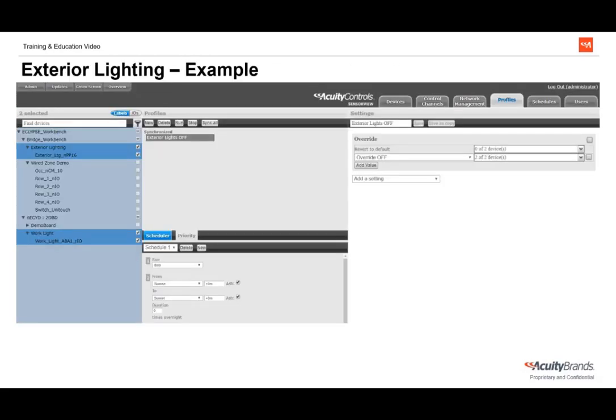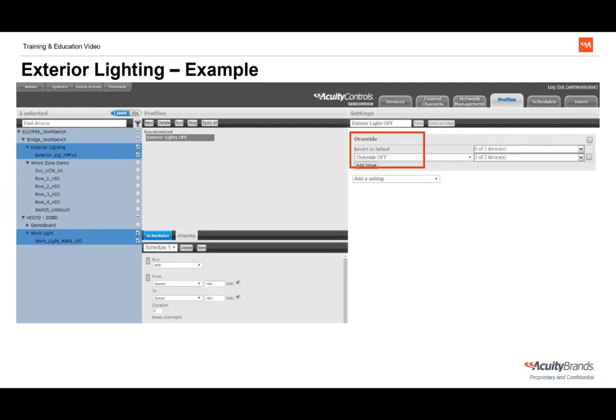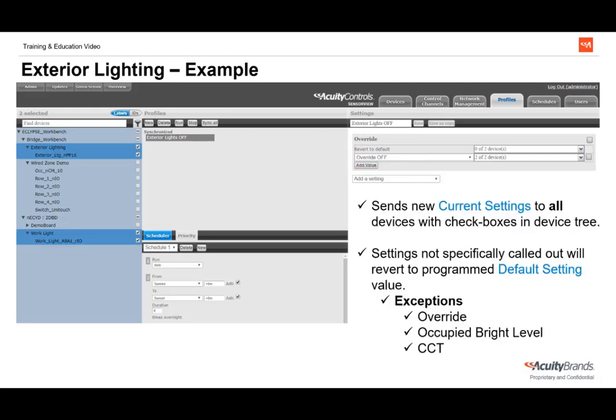Now let's see what setting this up in SensorView looks like, using our exterior lighting profile as an example. Profiles are created under the Profiles tab. Click New to create a new profile, select which devices you want included, and add the setting changes you wish to affect — in this case, just the override setting to off. Remember, we can use as many settings as needed. When run — from SensorView, a scene controller, or on a schedule — the profile sends new current settings to all devices in the device tree selected with checkboxes.